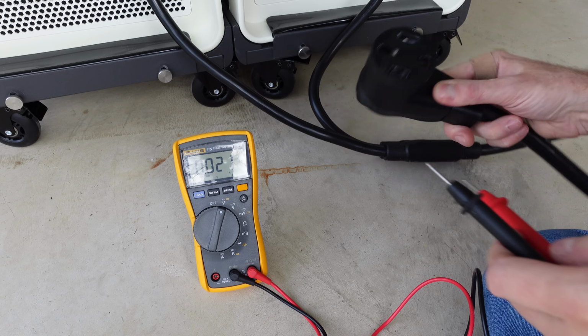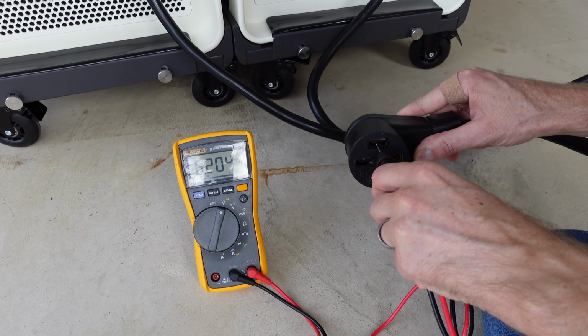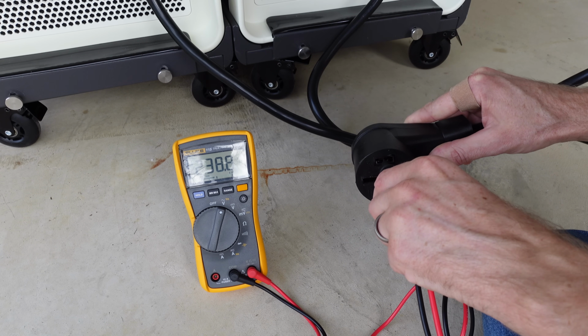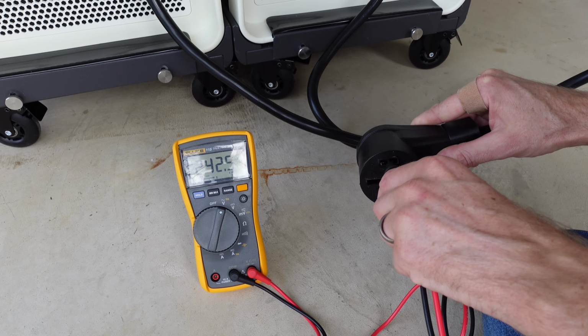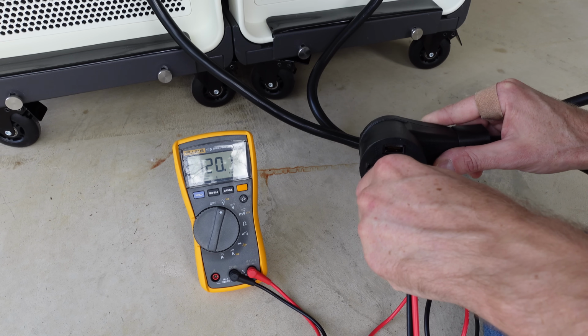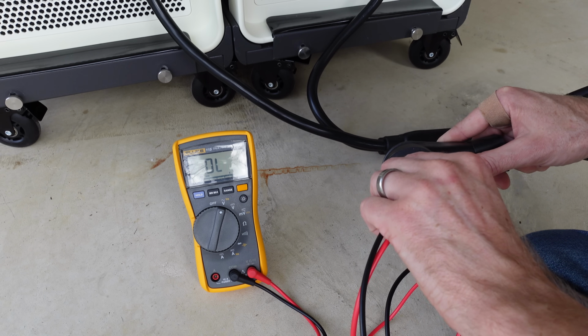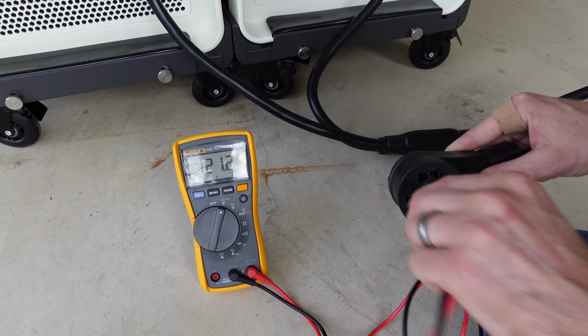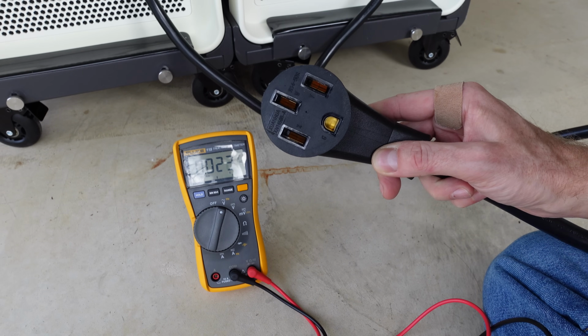Now I can take my voltmeter and insert the probes to leg 1 and leg 2, and I have 242 volts, bouncing around a little bit. Leg 1 to neutral is 120 volts, and leg 2 to neutral is 120 volts. So now we have a perfect US split phase output.